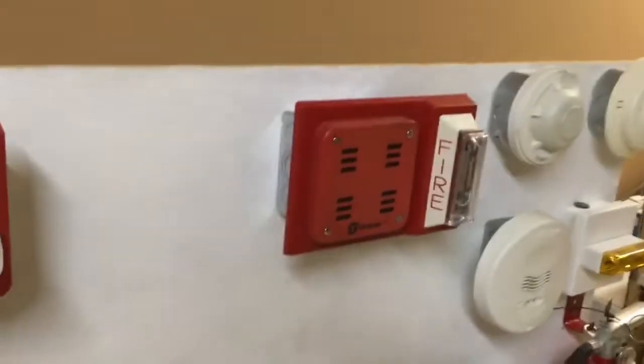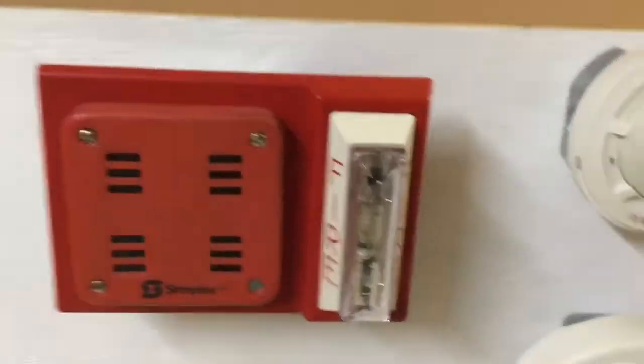There you go. As you can see, audible silence. This is flashing — it's 110 candela, it's quite bright. That is actually a Gentex strobe if you didn't know — you can see the same strobe you'd find on a Gentex SHG, just with a different casing. But yeah, let's do the 4251-20.